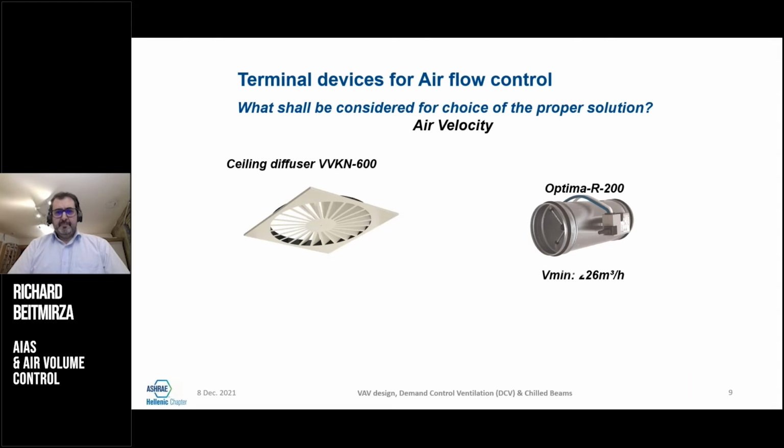What are some of the things that we have to be super careful when we use VAVs and demand control that I think is important. It is not only from the air handling unit to the chillers, but we have to go all the way down to the terminal devices. When we use a VAV and we go to the Vmin or the minimum ratio that we need to do, and we're still using delta T's that are higher than 6 or 7 degrees, we risk to have difficult air dumping.